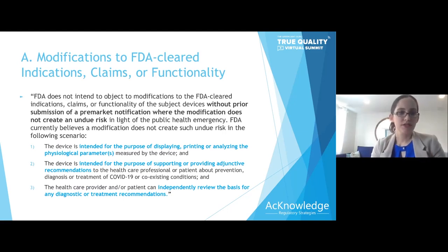So there are three parts to this guidance document; I've broken them into A, B, and C. This is a little redundant, so I'll go through it quickly. The modifications to FDA-cleared indications, claims, or functionality—again, they do not intend to object if you decide to modify your indications, claims, or functionality, and you do not need a pre-market notification if your device does not create an undue risk. They do have a list of undue risks in the guidance document that you should check out, to make sure you're not tripping that list.